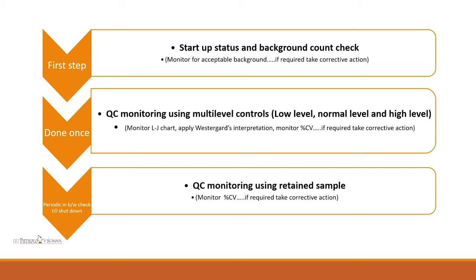The first step after entering the laboratory is startup and background check. In the background check, we run the machine blank — all values obtained should be zero. If they are not zero, there is a problem with the machine and it is not in control, and we must take necessary corrective actions.